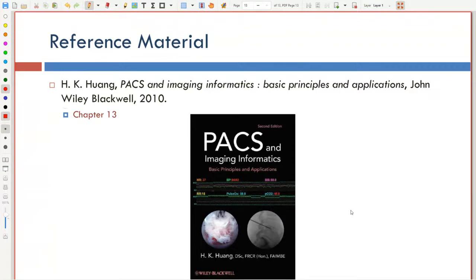You have to ensure that you're compatible with the other systems, because you have no guarantee that the other systems will be exactly the same as yours or from the same company as yours. So it's very important to make sure that you use standards like HL7 and DICOM and things of that sort, so that when you communicate information, you're communicating things that can be understood by the other systems, regardless of who the vendor was.